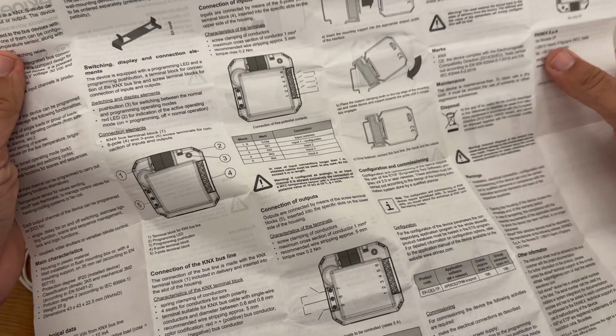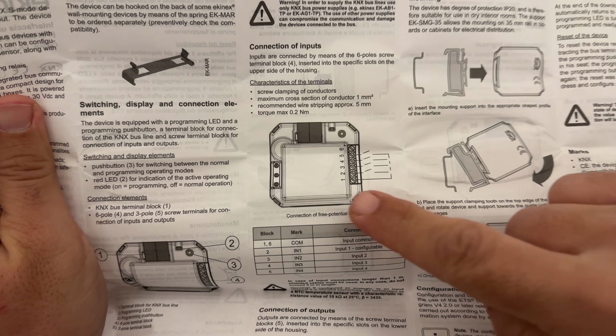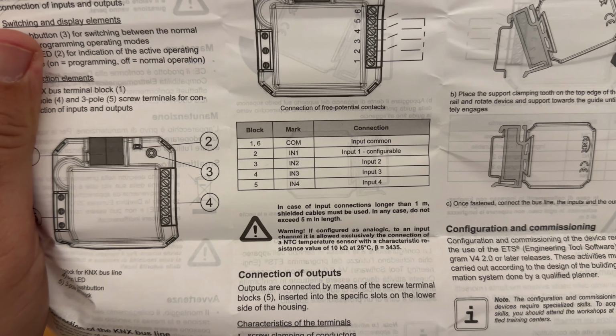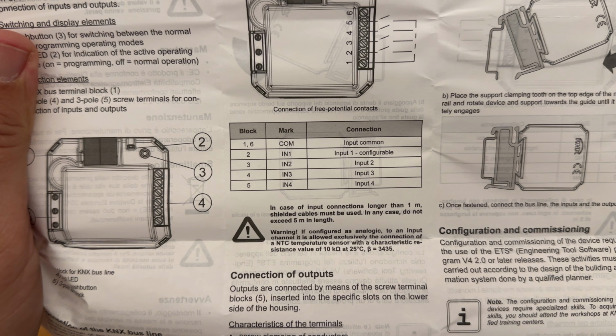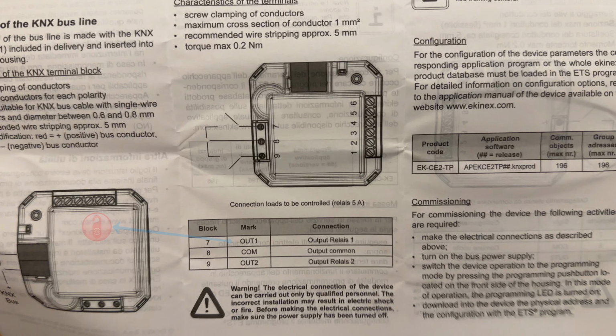Allow me to take a quick look at the installation guide to check the wiring. On the input terminal block, terminals 2 to 5 are the input terminals, while terminals 1 and 6 are the common terminals. For my project, input 1 will be connected to the card holder, input 2 to the Do Not Disturb button, input 3 to the Make Up Room button, and input 4 to the emergency button located inside the room's bathroom. For the outputs, the red DND LED goes to terminal 7, the green Make Up Room LED goes to terminal 9, and terminal 8 is the line supply for both LEDs.